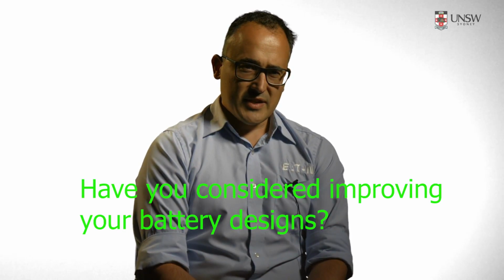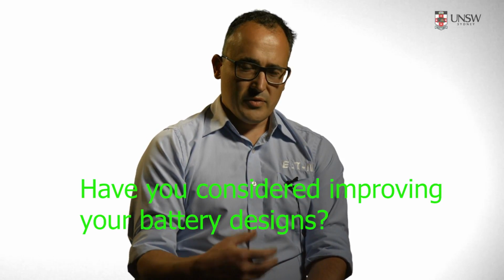And in the instance we had, the person wasn't wearing the appropriate protective equipment, so that resulted in the burns on their hand. And they also need to have the correct work procedures in order to not eliminate, but reduce the risk of shorting out the batteries. Recently we've changed our design to have an easy swap, or what we call an easy swap battery cubicle. So within the risk mitigation and the risk controls, what you want to do is try and eliminate the risk first of all. So what we've done is we've placed the batteries into battery packs that can easily be swapped in and out of the UPS systems by electricians and maintenance personnel. That eliminates that personal arc flash risk of the equipment itself.